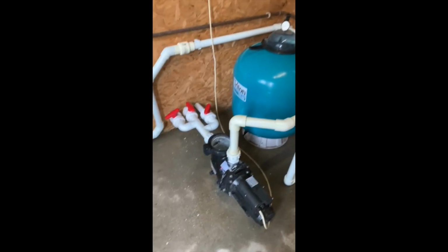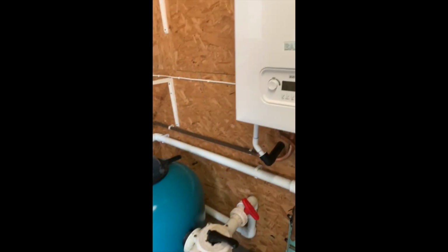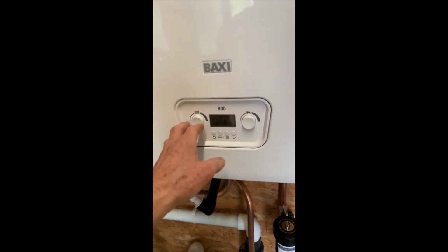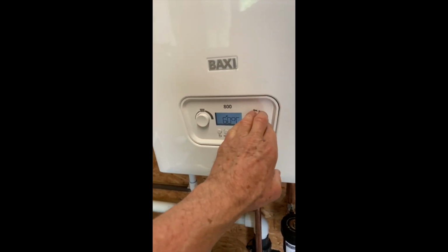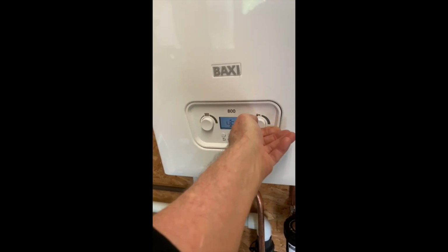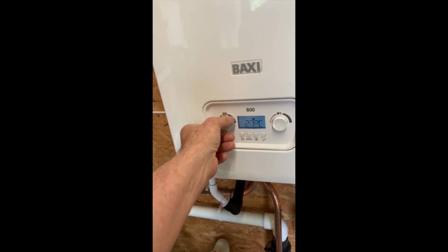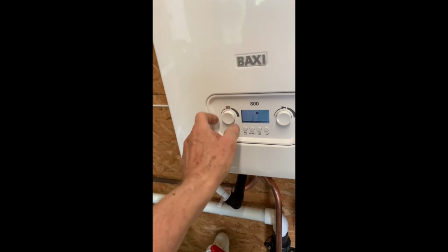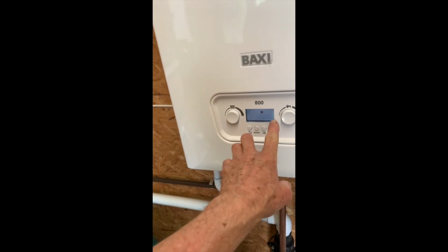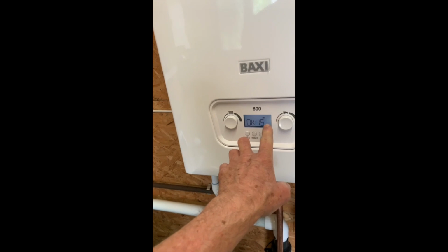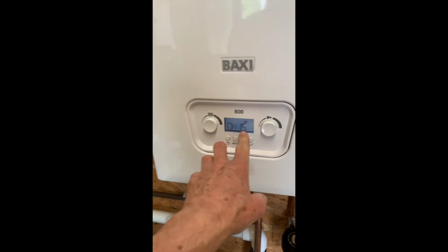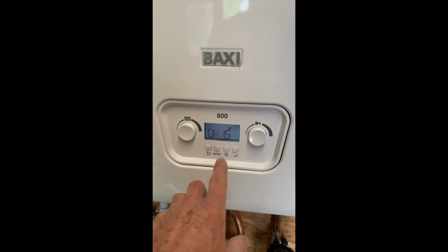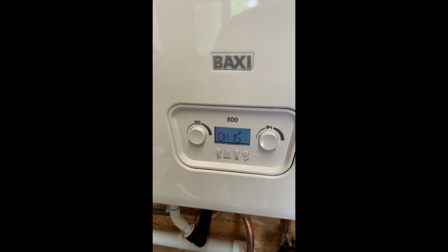So the circulation pump is off for a moment. We're going to look at the two controls we've got here. The one on the right is for a combi, so it's not normally used, so you can leave that all the way around to the left and it will go off. The one on the left is your internal temperature in the boiler. When you go around to off, it will come back with the actual pressure within the system, because it's a system boiler. It's showing 1.5 bar there that you can see. If you want to see it any time, just press the tick button and that's it.